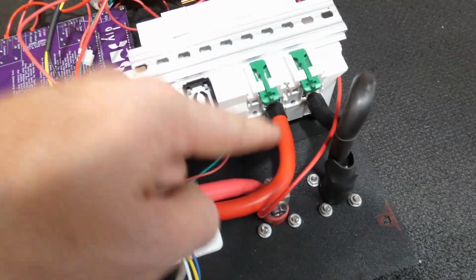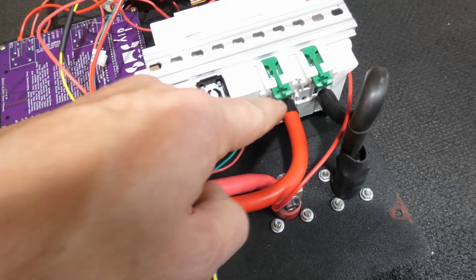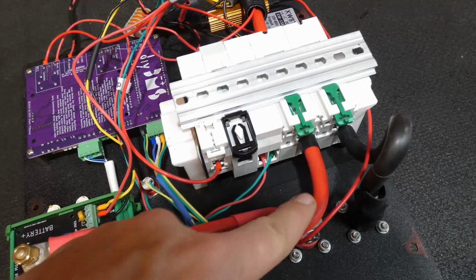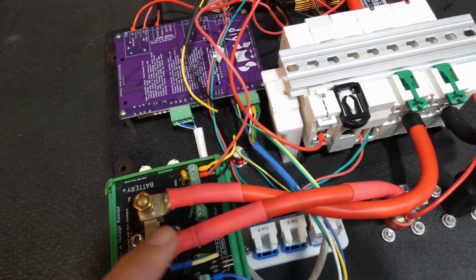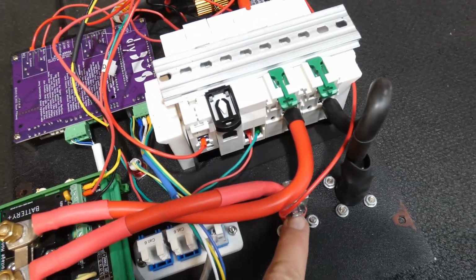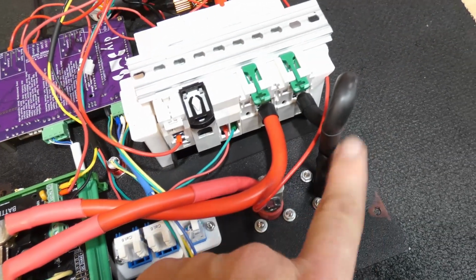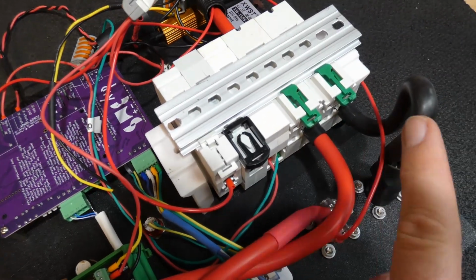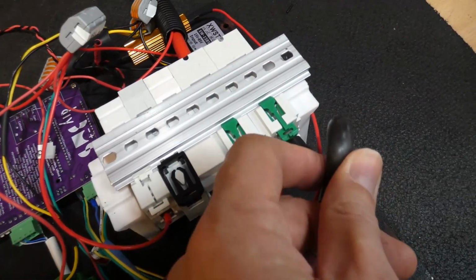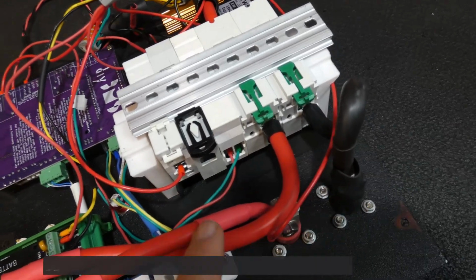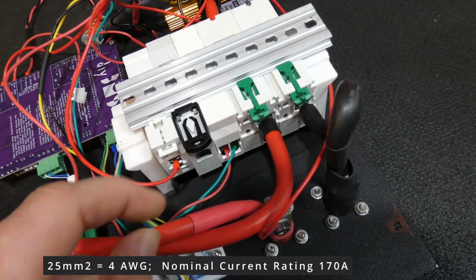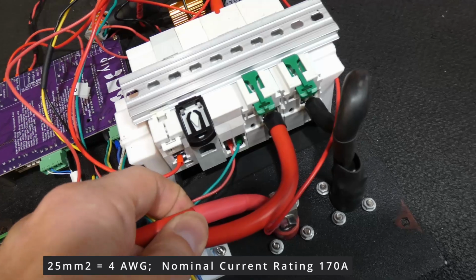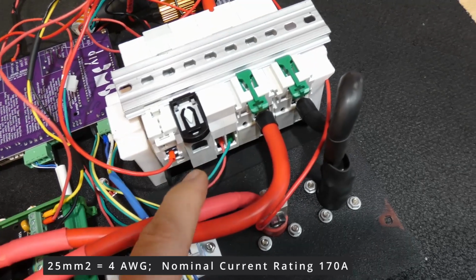And then we've basically got a loop between the incoming breaker, positive, into the current shunt, and then back out to the terminal, going over to the inverter. The negative's there, unfortunately I had to do quite a sharp loop to make that work, but it's quite soft silicon cable. This is all 25mm square cable, by the way, so suitable for about 150 amps, even though I only really need 60.